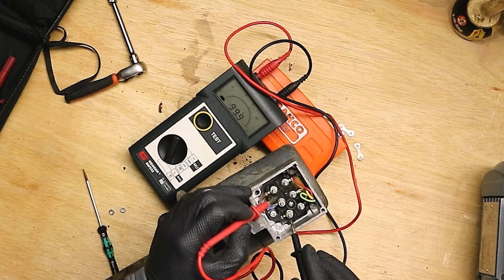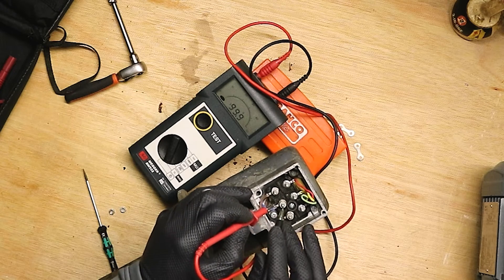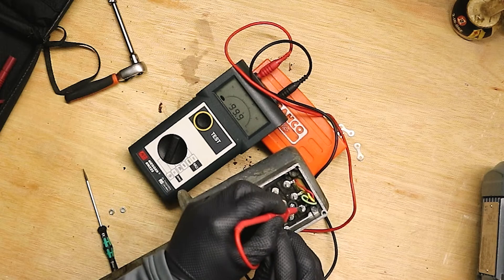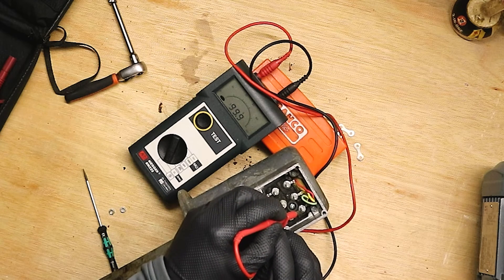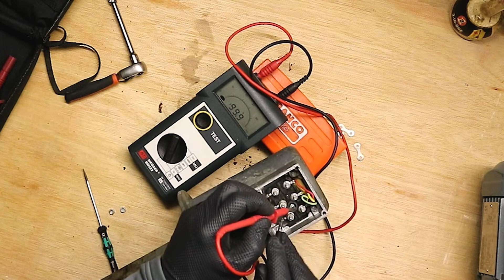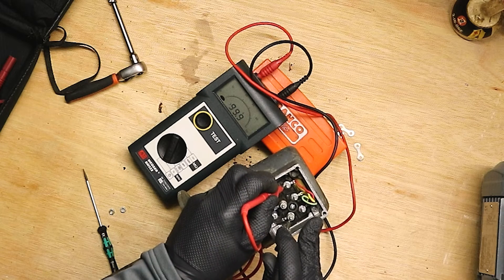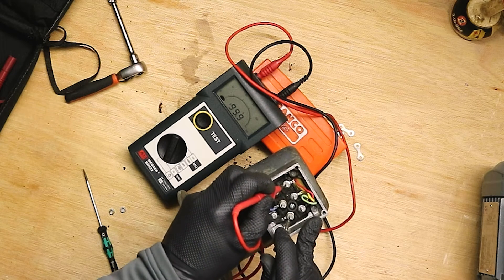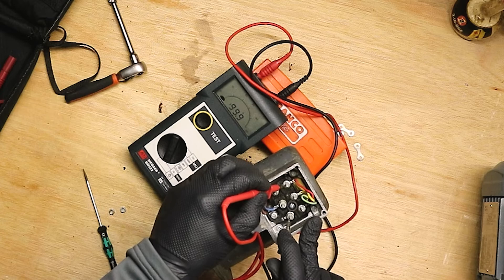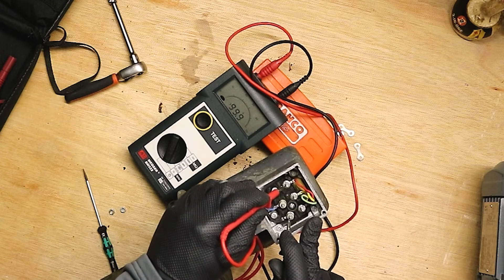Okay, so let's go to V1 and V2. Same. W1 and W2. Okay, so it looks like there's a problem in the motor and the windings have been severed.